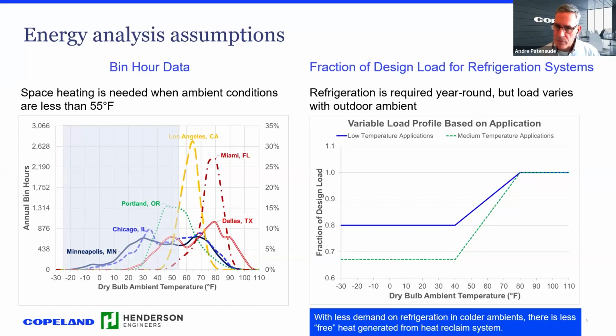The other thing we needed to consider is that refrigeration loads start to drop off as it gets colder outside, and there's a low temp application. So you've got a variable load profile as your ambient changes, which you can see on the x-axis of the chart on the right. As your ambient gets colder, the dark blue line represents low temperature applications; they kind of bottom out at 80% of full load when we reach 40 ambient or lower. But the medium temp starts to fall off around 75, and it goes a little bit below 70% of full load for medium temp when you're at 40 and below.